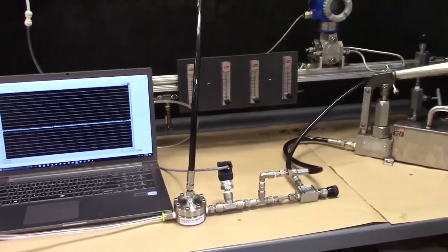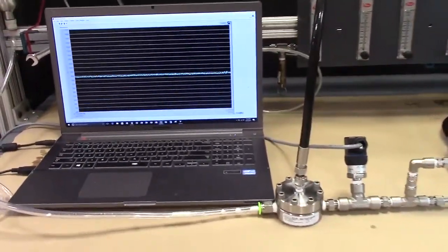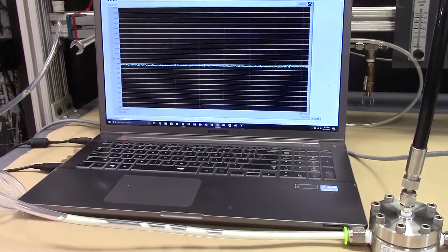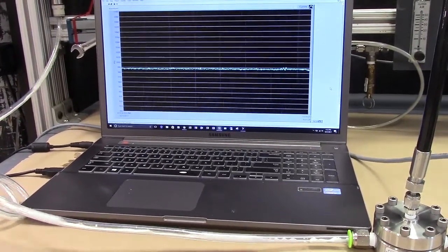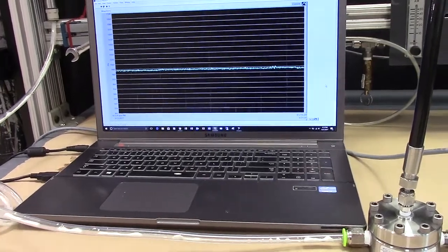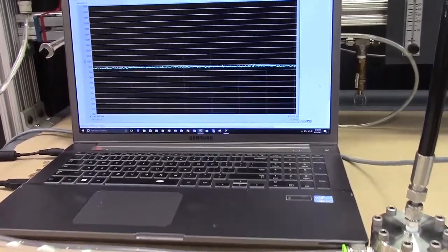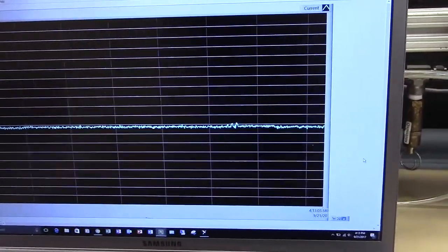So here we have the Equilibar back pressure regulator. I'm flowing at around three liters a minute of nitrogen and I introduce three pulses of liquid to the system. Interestingly enough we don't see any inlet pressure change as a function of the introduction of liquid and we see the mixed phase fluid evolve through the regulator without any disturbance to the inlet pressure.